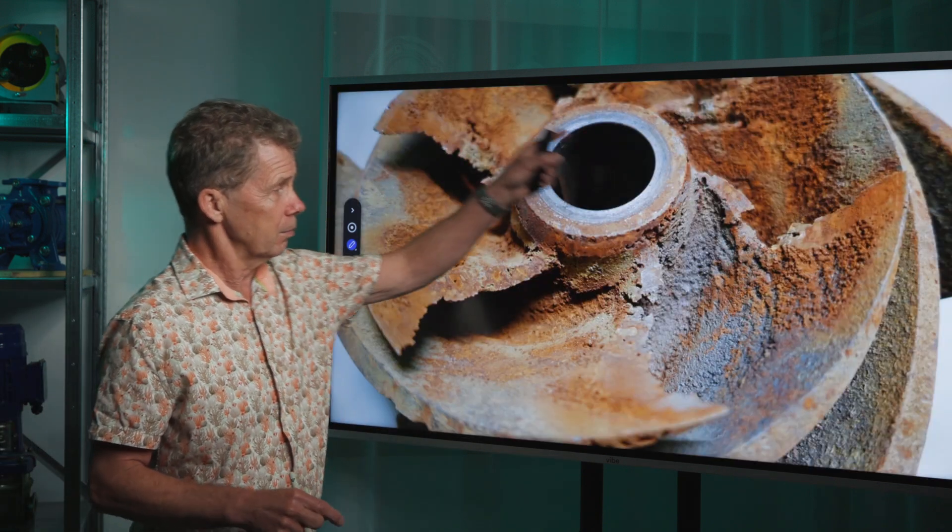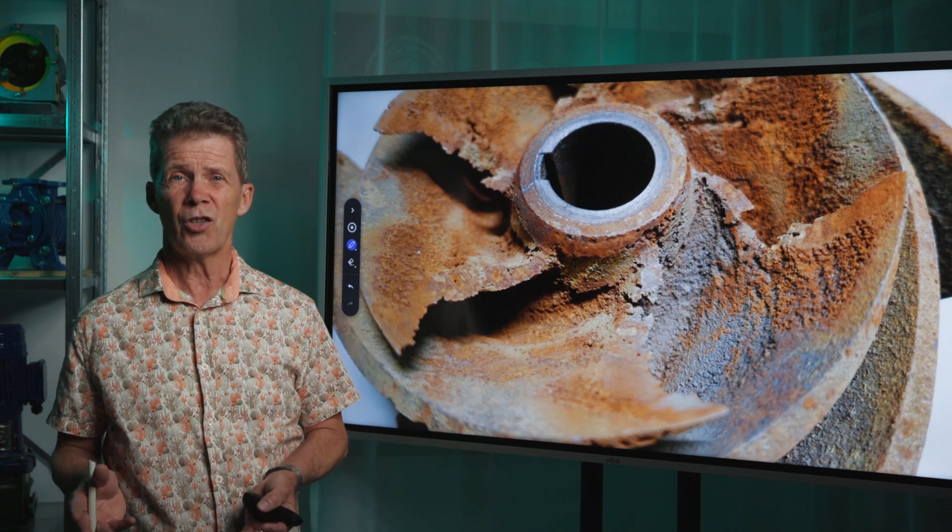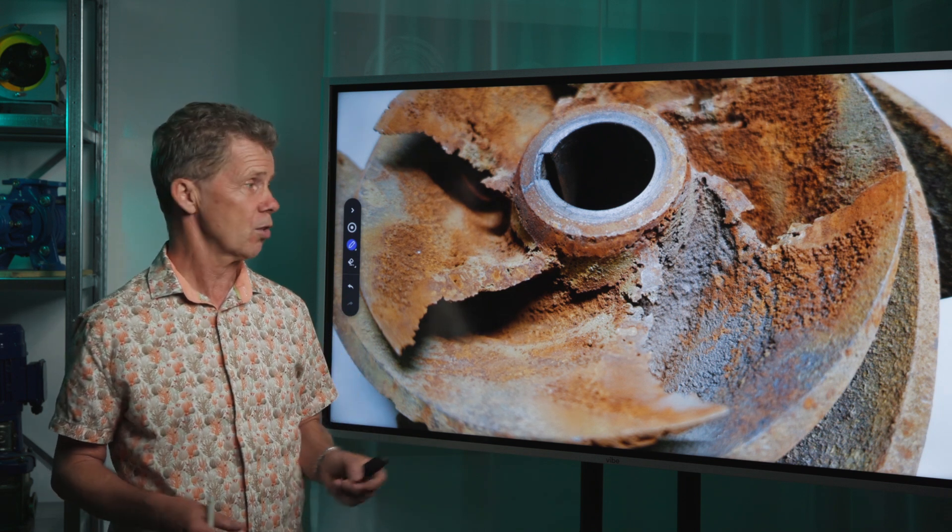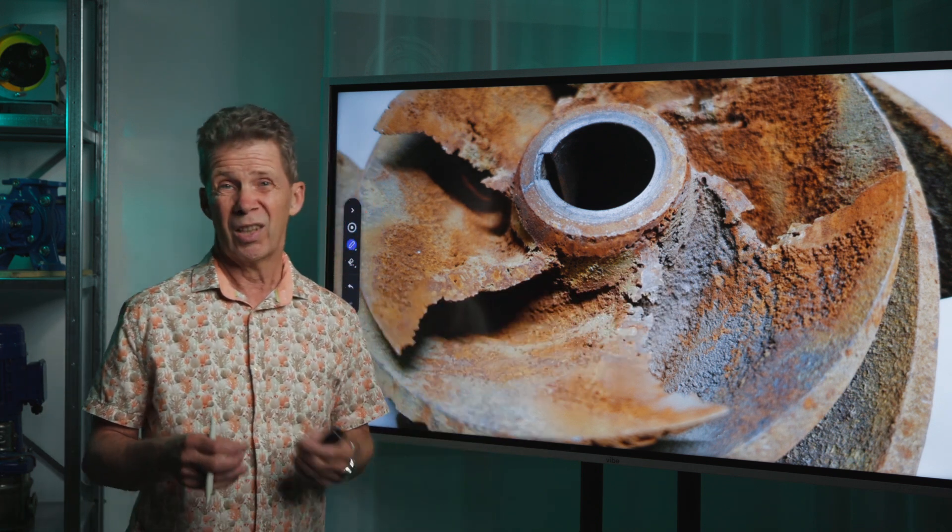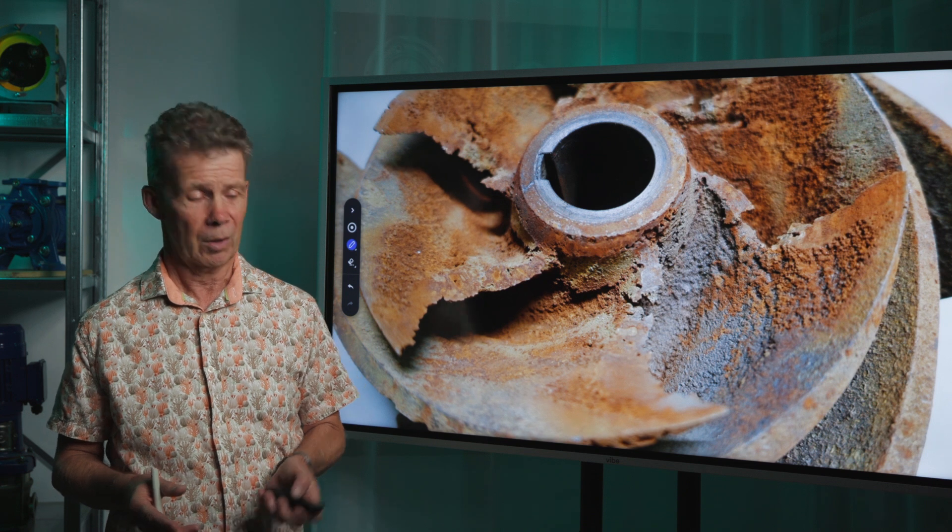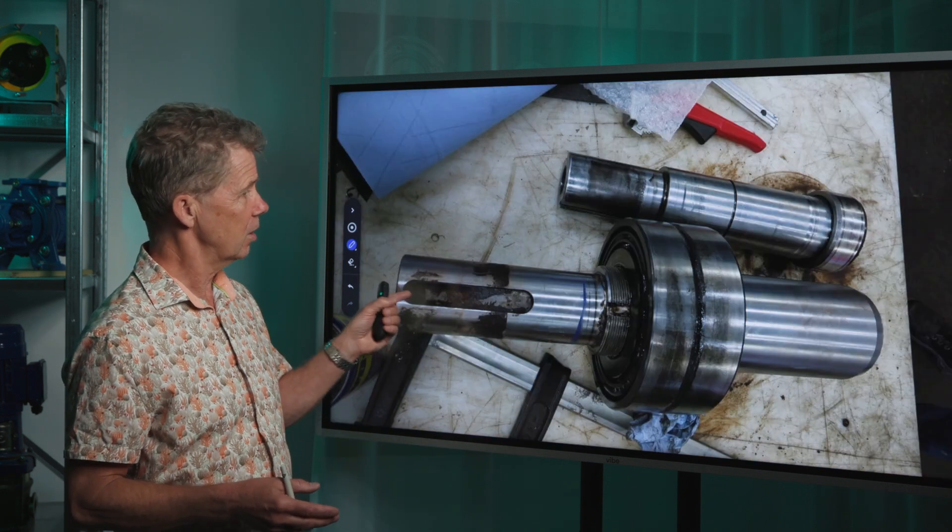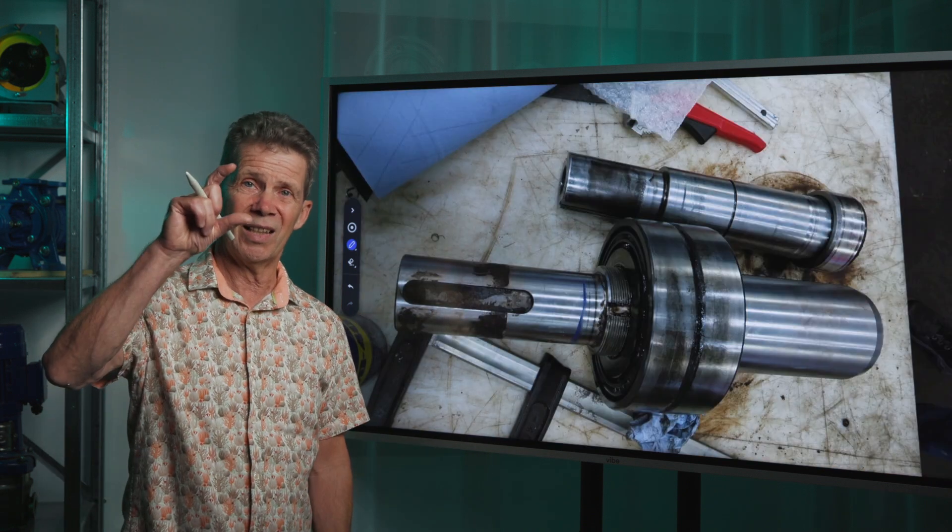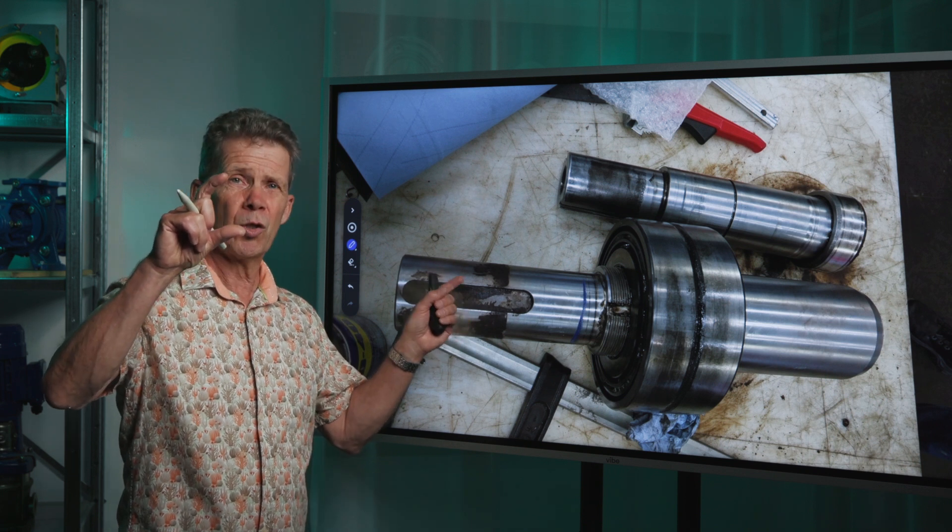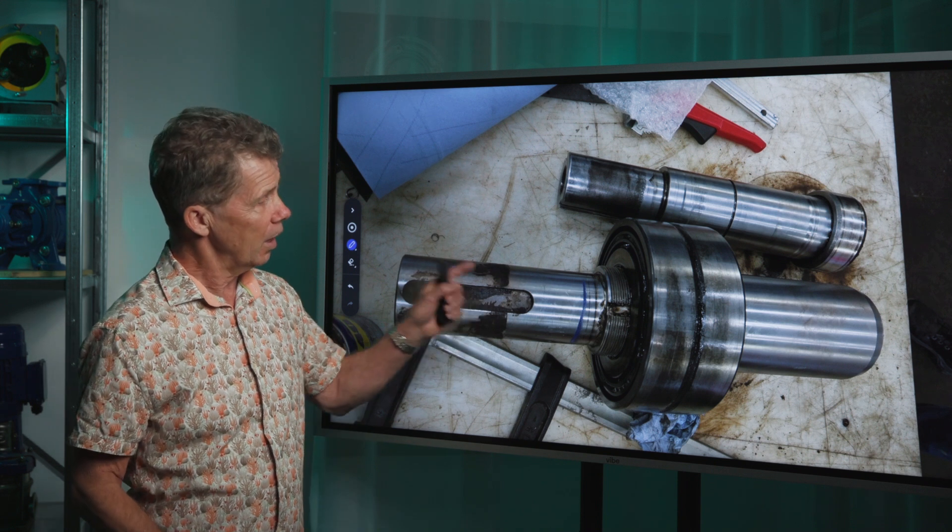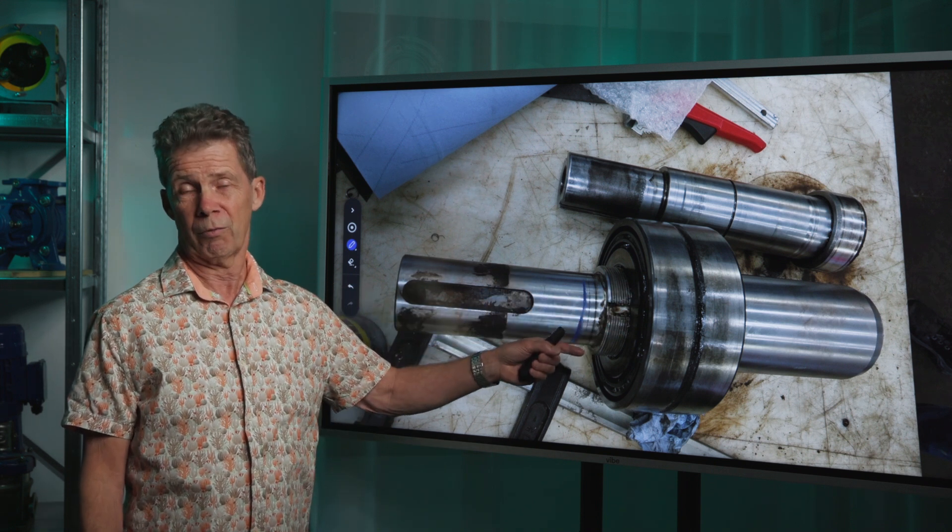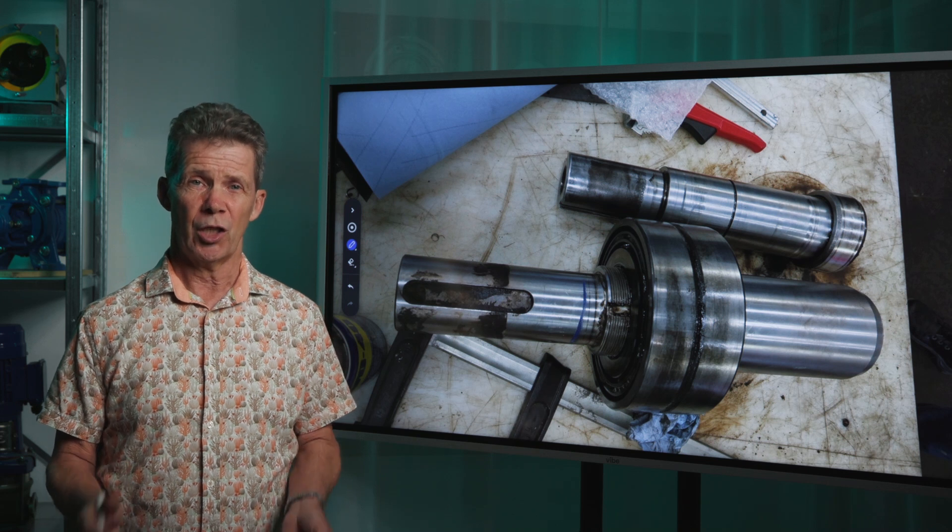This impeller has an operation time of six months and here you see clearly the holes of cavitation damage. But also here this shaft has a diameter like this. This pump was only in operation for six months and here the weakest part was the pump shaft. So cavitation forces are very high. But why do we get cavitation?